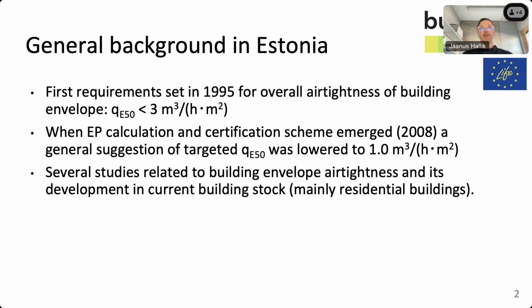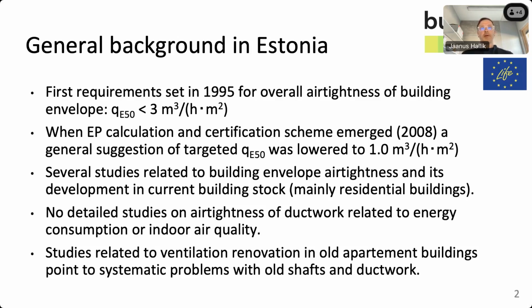There have been several studies related to the building envelope airtightness and its development in the current building stock in Estonia, but they mainly deal with residential buildings, where the indoor climate, the building physics and the moisture problems inside the structures are really important in our climate. There are no detailed studies on airtightness of the ductwork related to energy consumption or indoor air quality in Estonia, but we have a lot of smaller studies related to ventilation system renovation in old apartment buildings, which all point to systematic problems with old shafts and ductworks. Usually this means that the airflows are unbalanced, the system is quite noisy, and the airflow rates are reduced in operation compared to the design documentation.